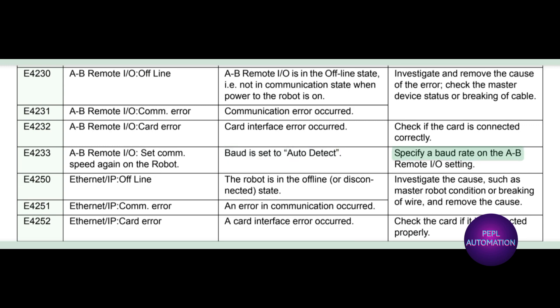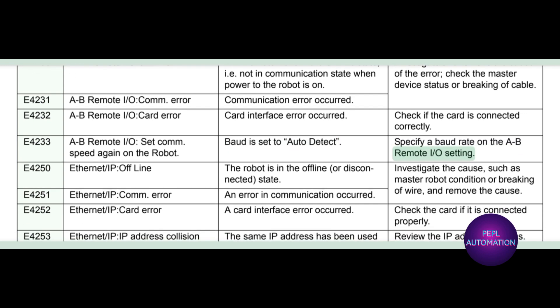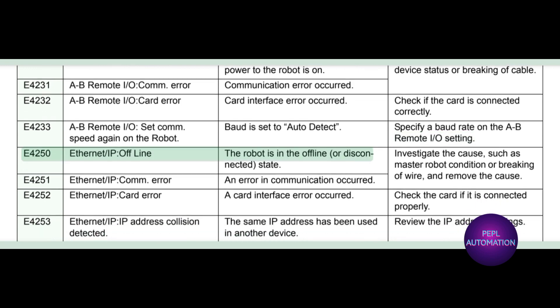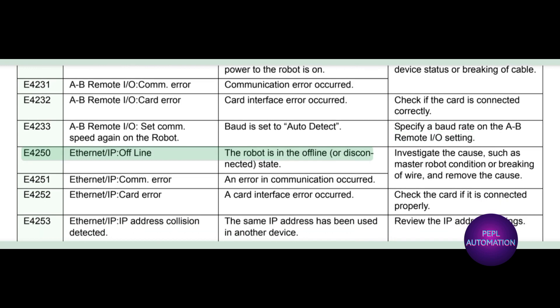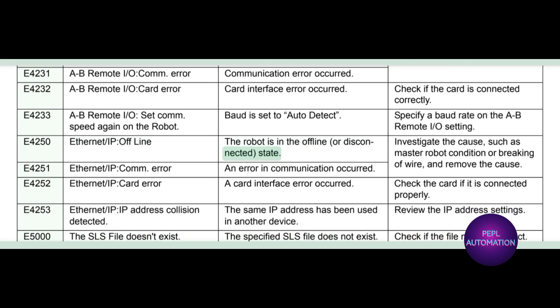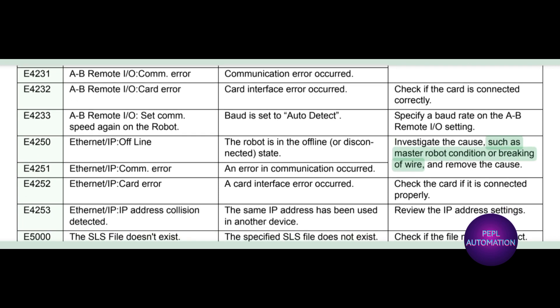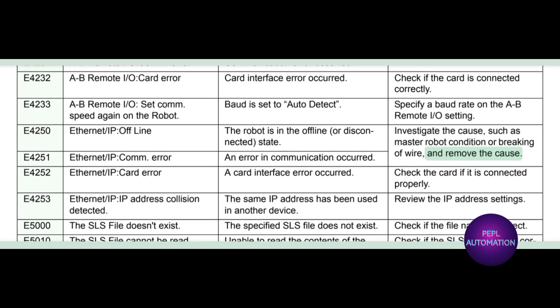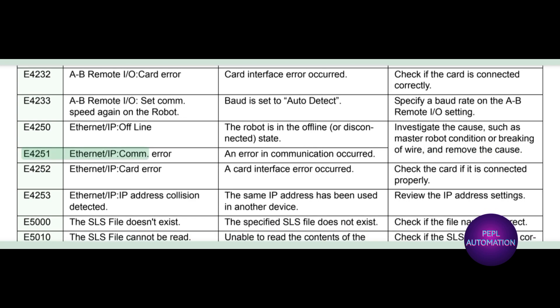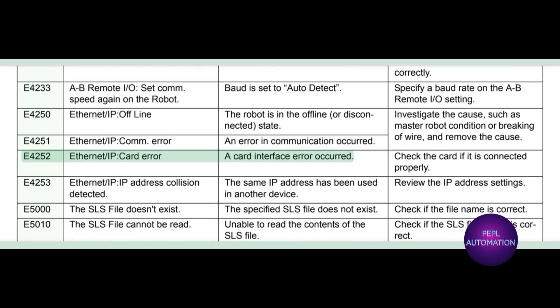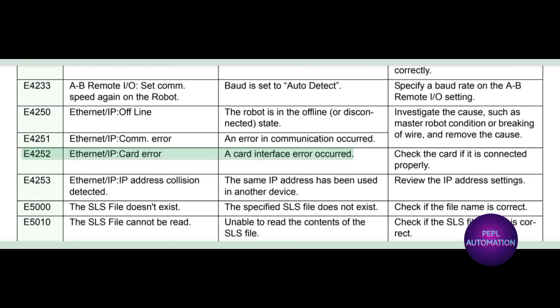E4233 AB remote IO: set com speed again. Baud is set to auto detect; specify a baud rate on the AB remote IO setting. E4250 Ethernet IP offline: the robot is in the offline or disconnected state. Investigate the cause such as master robot condition or breaking of wire and remove the cause.